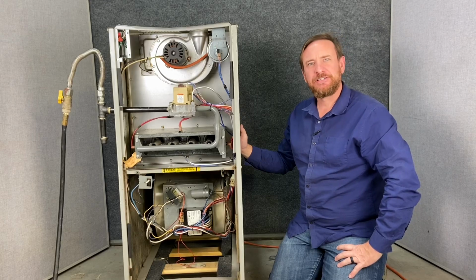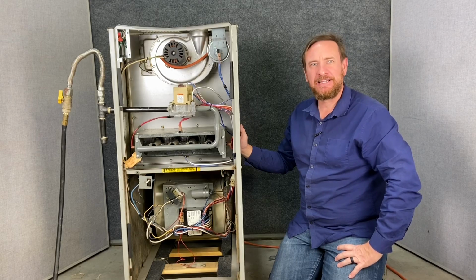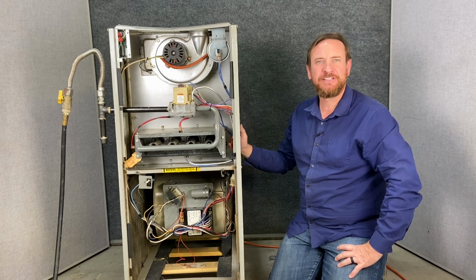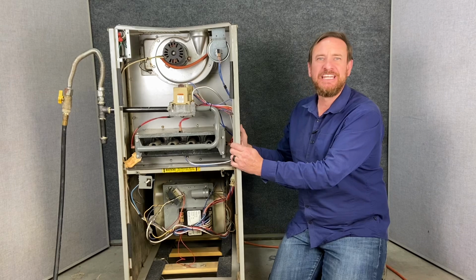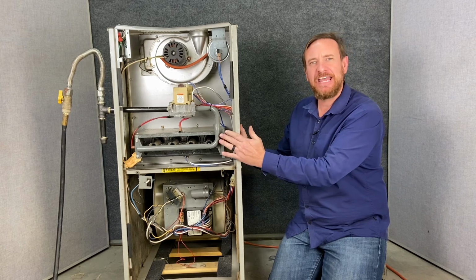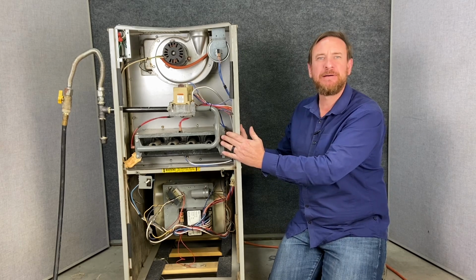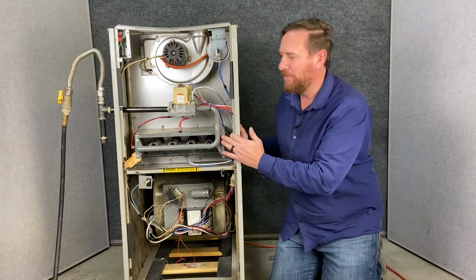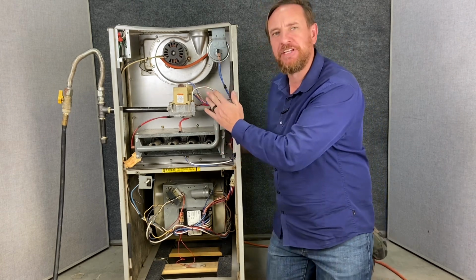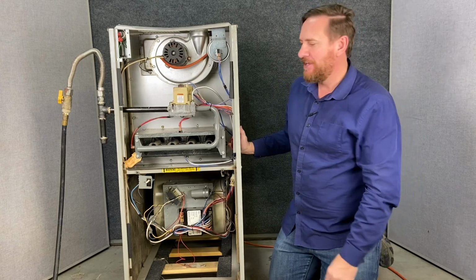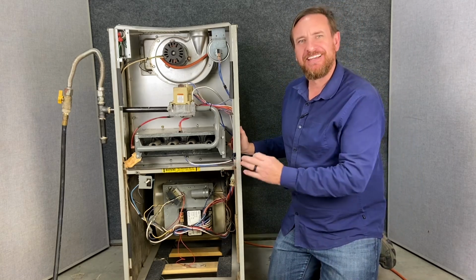So in the past, I've talked about standing pilot furnaces that had a pilot light burning all the time, and we talked about direct ignition, where we lit the main burners directly. This furnace is what we call an intermittent pilot system. It's still an 80% gas furnace, but instead of having that pilot light burn all the time, we simply light the pilot specifically before we light those main burners. So the sequence of operation of this furnace is a little bit different.